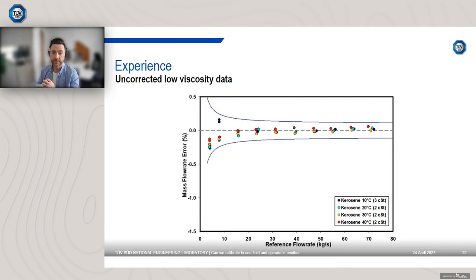So now I have some data to show you. I like to use this chart, so some of you may have seen it in my previous presentations or journal papers, but it's quite a nice set of data. On the x-axis we have reference flow rate in kilograms per second this time, rather than tons per hour. On the y-axis we have mass flow rate error, so that's the deviation in the device under test mass, the Coriolis meter's mass flow or totalised mass, compared with our reference mass flow rate or reference mass.